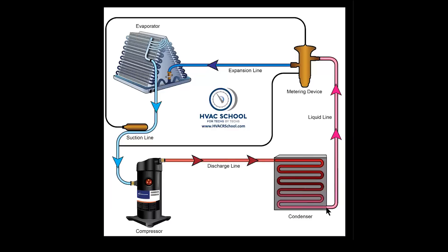It all depends on where you're measuring pressure — typically here at the outlet of the condenser at the liquid line service port on a residential system. So why does a liquid line restriction cause low head? When you have a restriction, not as much refrigerant can come through the evaporator and back. Refrigerant density decreases, there's less for the compressor to pump, and less heat is being added to the system. Think of the evaporator as a heat absorber and the condenser as a heat rejector. If you don't have as much refrigerant going into your heat absorber, you're not absorbing as much heat, not bringing as much heat back to the compressor, and therefore not as much heat going into the condenser — so there's less heat to reject and you don't have high head pressure.